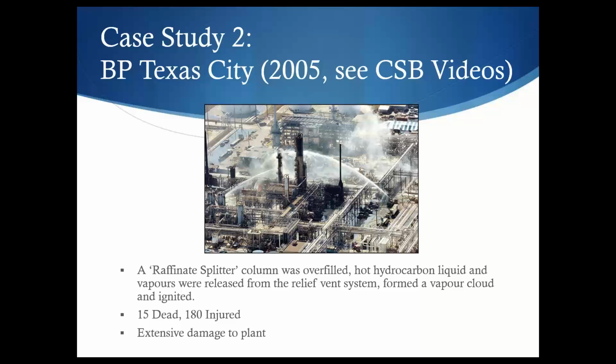And unfortunately, we weren't so lucky as the other guys. They actually happened during the day, and there was a meeting going on in trailers that were parked fairly close to the incident. You can see them in this picture just behind where they're spraying the water onto the column. And you can also see the vent stack there. That was the one that overfilled, and that's actually where the loss of containment was.